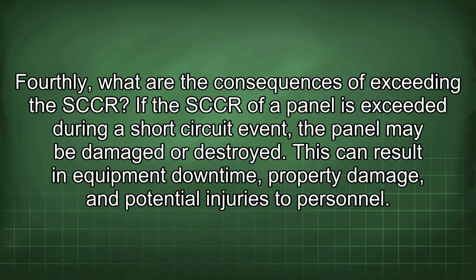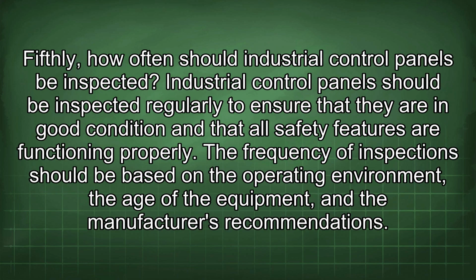If the SCCR of a panel is exceeded during a short-circuit event, the panel may be damaged or destroyed. This can result in equipment downtime, property damage, and potential injuries to personnel. Fifthly, how often should industrial control panels be inspected? Industrial control panels should be inspected regularly to ensure that they are in good condition and that all safety features are functioning properly.